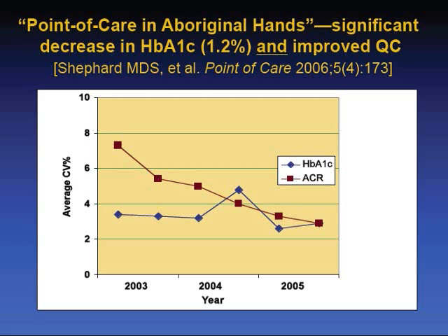This figure shows the average imprecision achieved for external quality assurance of hemoglobin A1c and urine albumin creatinine ratio point-of-care technology in all 4 participating services over the following years. A1c and albumin creatinine ratio levels of imprecision readily met the precision goals, except for one time point in A1c during 2004.